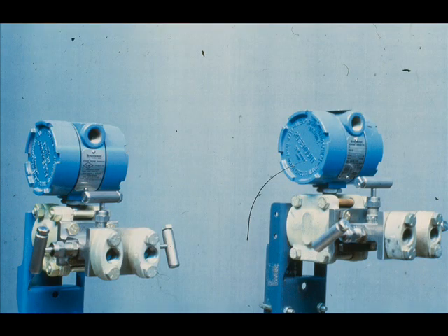The transmitter with 'C' for the output code in the model number has a 4 to 20 milliamp output that is proportional to the square root of the input — it is called a square root of the delta P flow transmitter. Even though it looks like the other transmitters, it has a different amplifier board, calibration board, and a different calibration procedure.